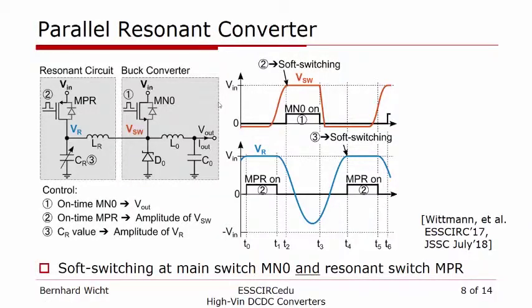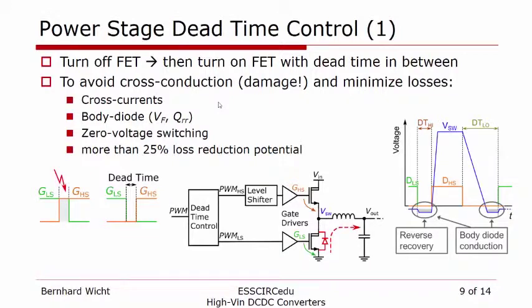The second concept I would like to discuss is dead time control. Looking again at the DC-DC converter power stage half-bridge: we first want to turn off one device before turning on the other, otherwise we get cross-currents which may cause damage. However, we cannot extend the dead time too long because other loss components come in, like body diode conduction and reverse recovery. There is an optimum dead time which gives minimum losses, with a potential to reduce losses by more than 25%.